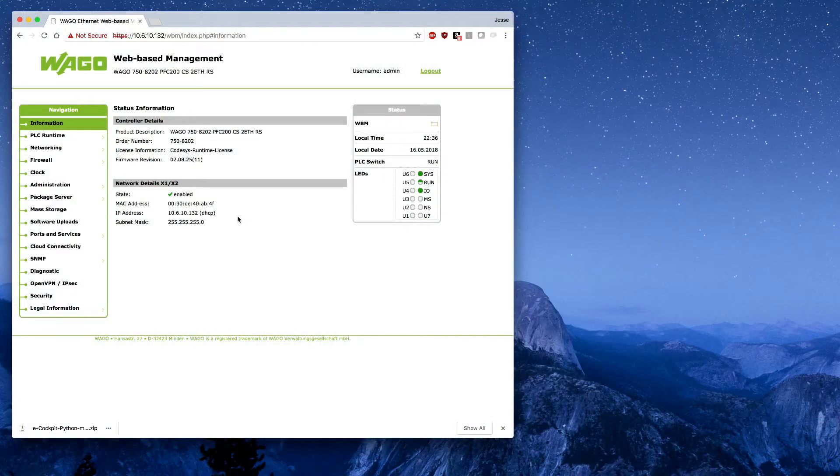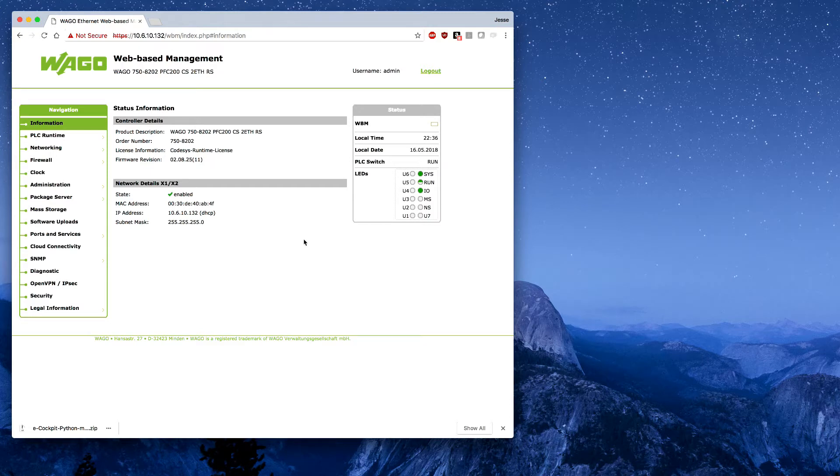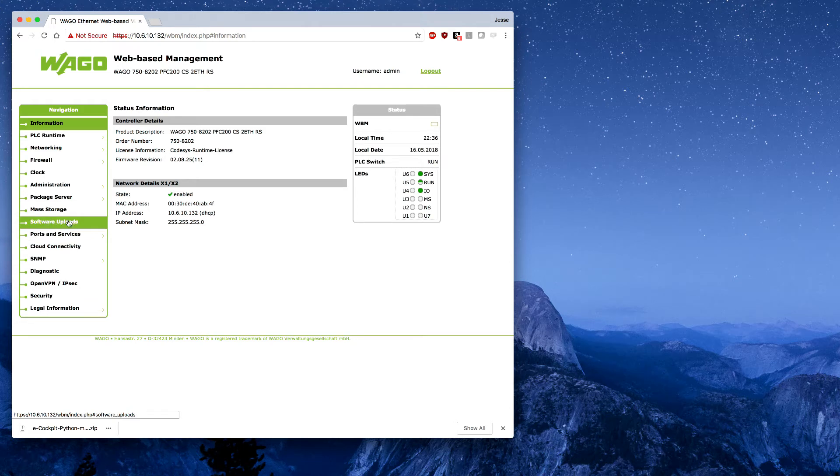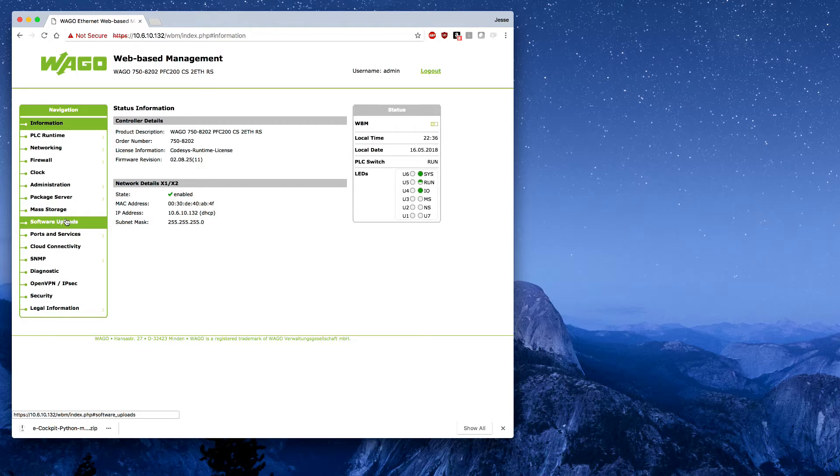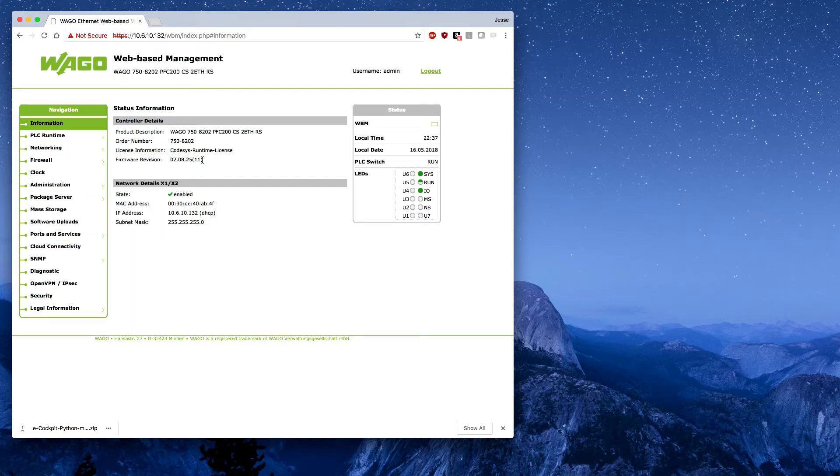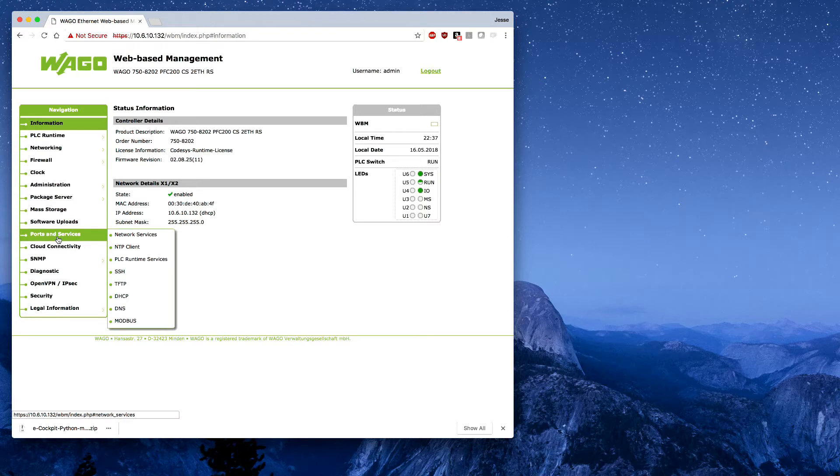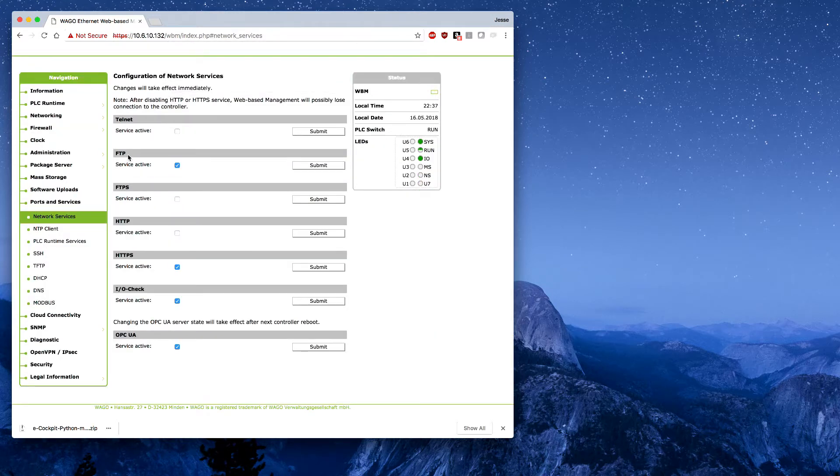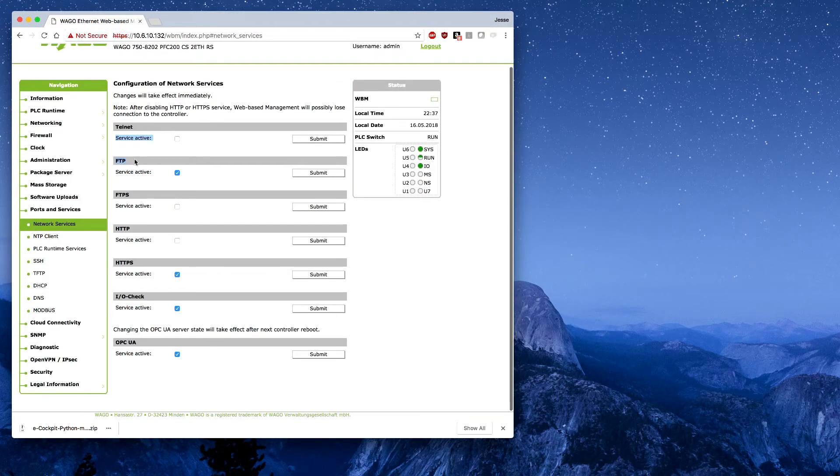The first thing I'm going to do is go to the web-based management of the PFC because I want to enable the FTP port. I could use the software upload to upload the IPK but I prefer to do it in FTP and then push the install through the shell. I'm using firmware 11 here, nothing else other than standard firmware, standard size and all that. So no resizing like Node-RED required. I'll go to ports and services, select network services, and just want to make sure that FTP is enabled here.